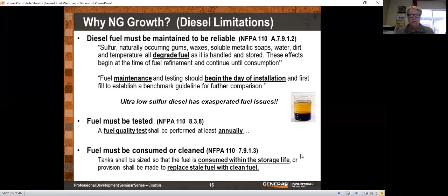For emissions. But because we have the low sulfur diesel, the sulfur had a very strong ability to cause these microorganisms not to grow. And when we take that sulfur out, then the microorganisms start to grow. We end up with these microorganisms generally between the water, and there's always some water in a diesel fuel tank on the bottom. At that interface between the water and the diesel fuel, you get bacterial growth, and then that comes up and clogs the fuel filters. Another reason why diesel generators have problems if they're not maintained very meticulously.